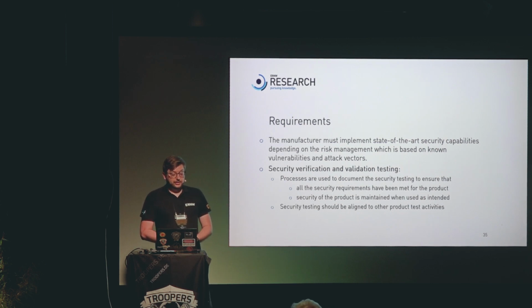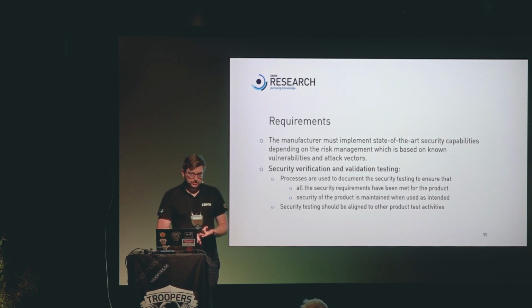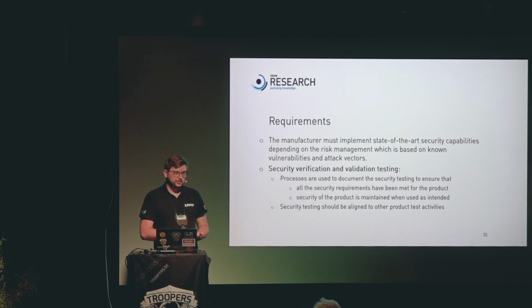It also demands intense security verification and validation testing processes, and you have to document that. As with the previous law, notified bodies will audit that when you want to market your device. The best way to document that, from the MDCG perspective, is to show that you are doing assessments. The MDCG also says that you have to do fuzz testing, code scans, pen tests, and other things you never read in any of the other guidances before. So it is actively demanding this of the manufacturers.